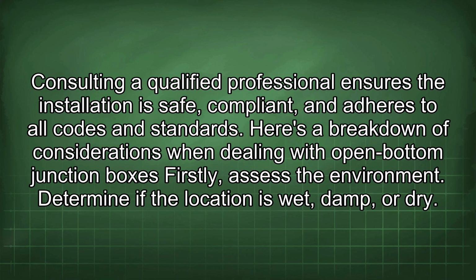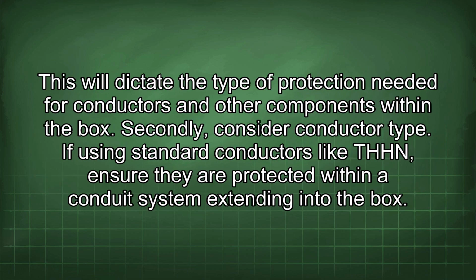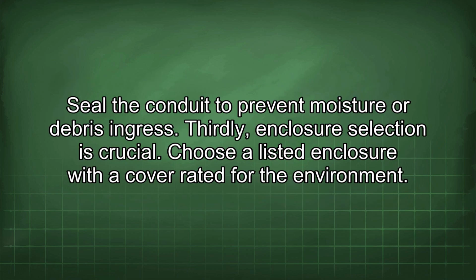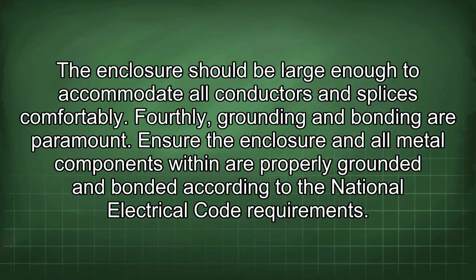Here is a breakdown of considerations when dealing with open-bottom junction boxes. Firstly, assess the environment. Determine if the location is wet, damp, or dry. This will dictate the type of protection needed for conductors and other components within the box. Secondly, consider conductor type. If using standard conductors like THHN, ensure they are protected within a conduit system extending into the box. Seal the conduit to prevent moisture or debris ingress. Thirdly, enclosure selection is crucial. Choose a listed enclosure with a cover rated for the environment.